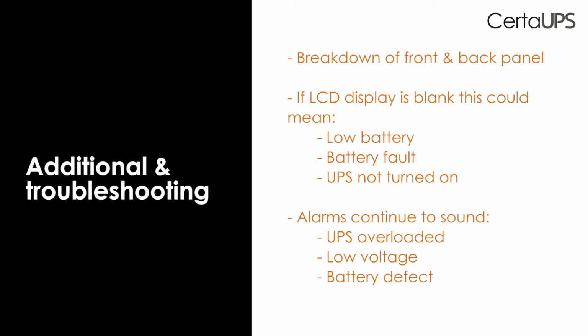You've then got a breakdown of the front panel and back panel, and then the bottom is the troubleshooting. If nothing is displayed on the front panel, that can be one of three things: a low battery, a battery fault, or the UPS is not turned on. The solutions to each would all be shown to the right hand side.